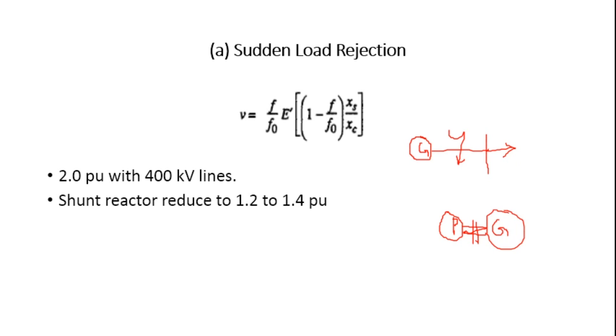But initially, both the frequency and the voltage are going to increase. The approximate voltage rise is given by the equation: V = (f / f₀) × E' × [1 − (f / f₀) × (Xs / Xc)], where Xs is the reactance of the generator — the summation of the transient reactance of both the generator and the transformers — and Xc is the capacitive reactance of the line at the increased frequency.